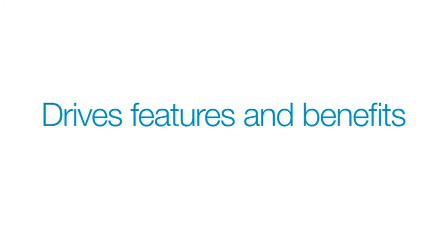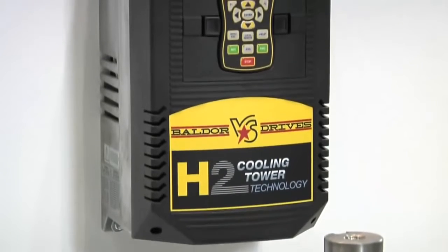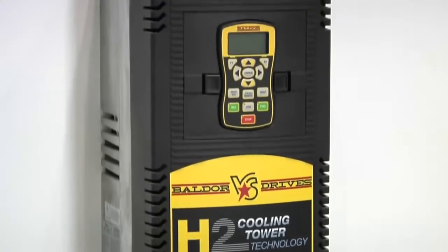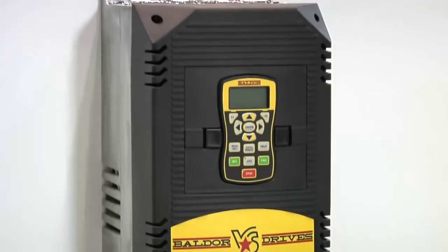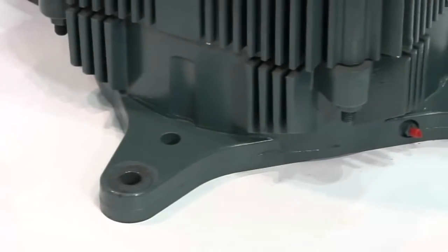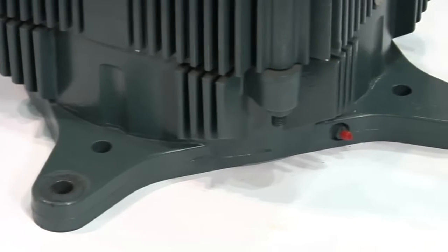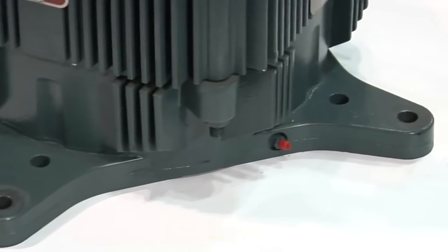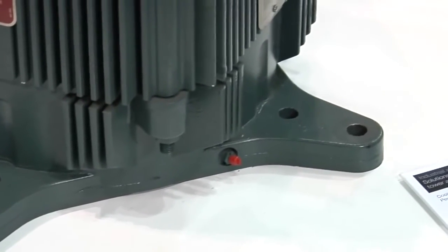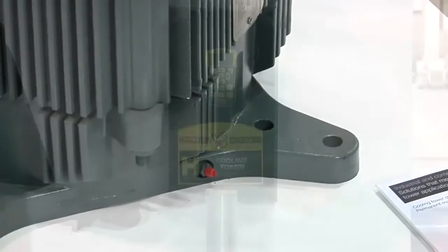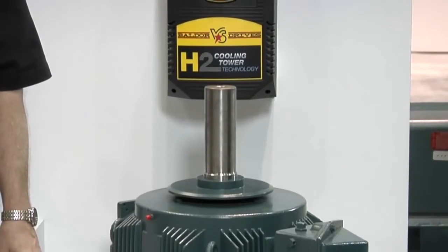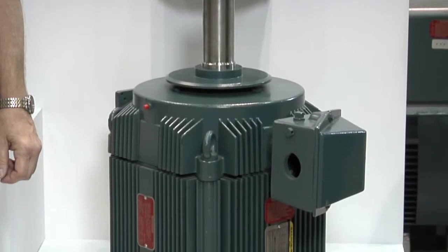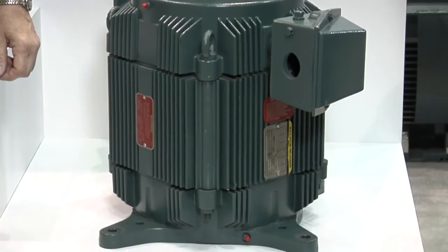When used with a variable frequency drive, the motor and drive combination eliminates the need for a gearbox and runs the motor at the optimum speed needed to cool the circulating water. We developed a special bottom bracket that matches the footprint of many common gearbox designs. This makes the motor a fast and simple replacement for existing gearboxes. To handle the high axial fan thrust loads, we used high thrust capacity bearings in the bottom bracket.